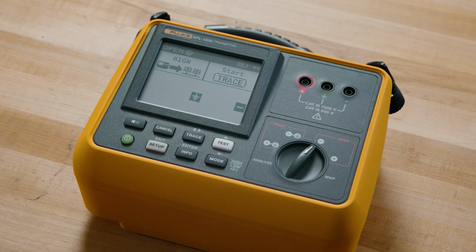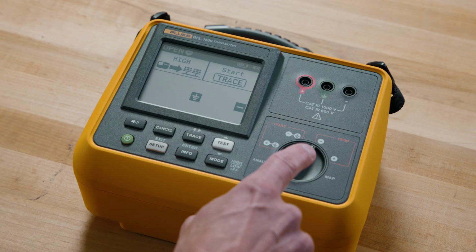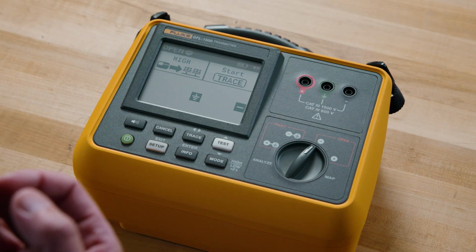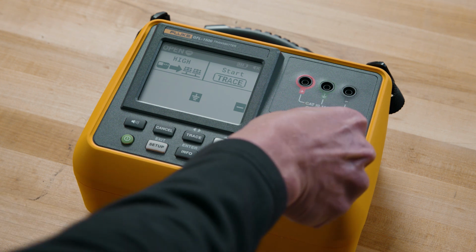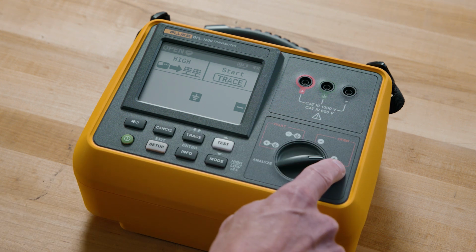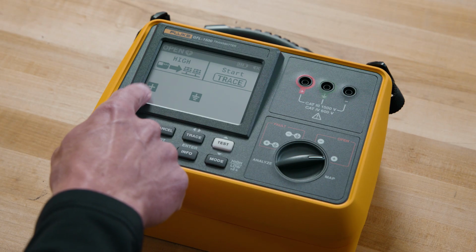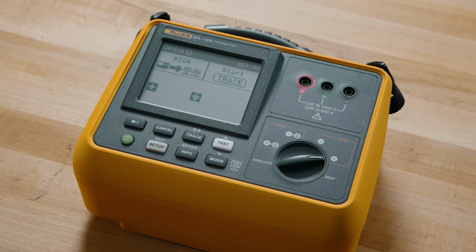And remember, in open mode, I need to isolate that circuit from other circuits. So in most cases, you're going to do that by removing positive fuses, which means I'm going to want to inject the signal on the negative side. If I have fuses on the negative side, I can isolate there and switch to the positive function. And you can see that changes here. We have the positive symbol here and the positive symbol at the top as well.